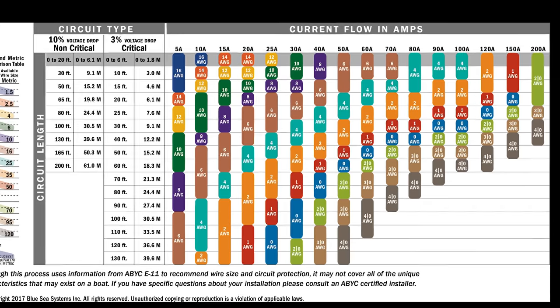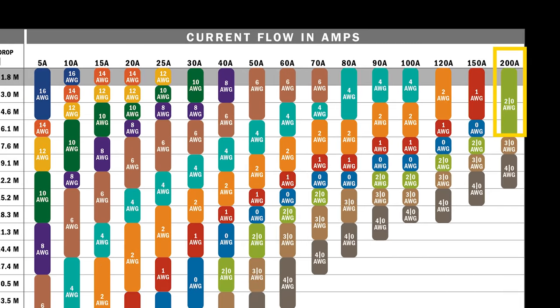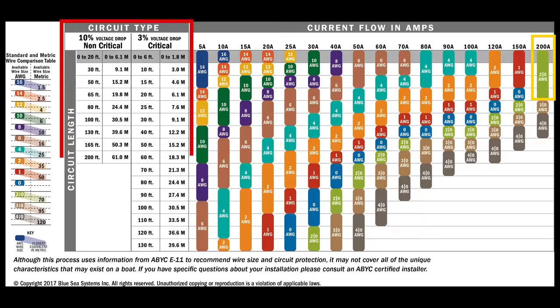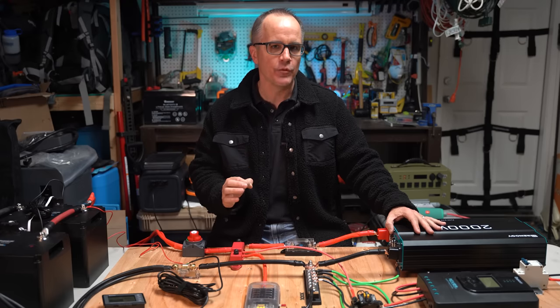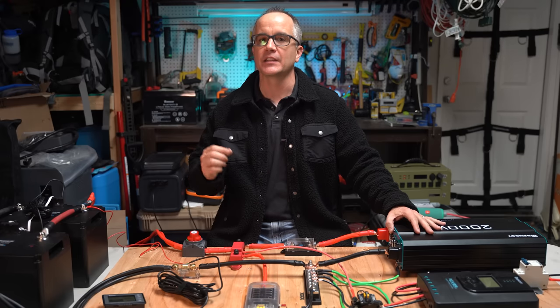From the chart, we see that we need a 2/0-gauge wire to support 196 amps. Also, pay attention to the distance. In the chart, it shows you the size of the wiring based on how long your wiring will be. As distance increases, the wiring will start increasing in size. Since our run from the battery to the inverter is under 3 meters, 2-gauge is perfect. So now we know the size of the cable that we're going to need to connect the inverter to the battery.